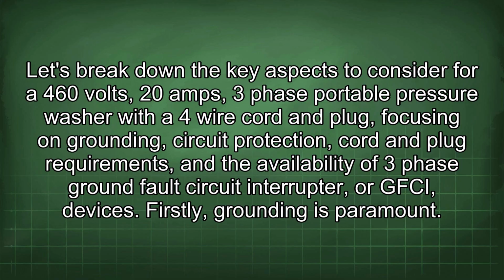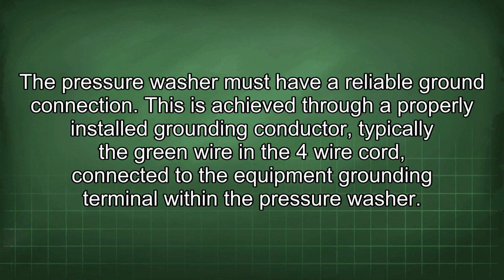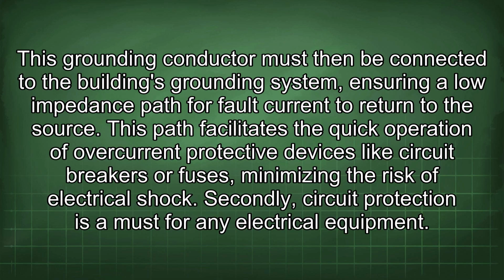Firstly, grounding is paramount. The pressure washer must have a reliable ground connection. This is achieved through a properly installed grounding conductor, typically the green wire in the 4-wire cord, connected to the equipment grounding terminal within the pressure washer. This grounding conductor must then be connected to the building's grounding system, ensuring a low impedance path for fault current to return to the source. This path facilitates the quick operation of overcurrent protective devices like circuit breakers or fuses, minimizing the risk of electrical shock.